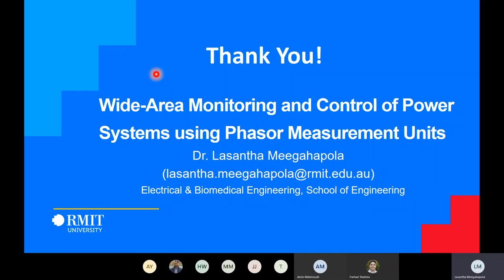I could give you one answer. Even in our test, we have shown 6 cycle latency in a certain case, from the measuring point to the real-time voltage stability analysis point. There could be latencies that go up to 4 to 5 cycles as well. But the algorithm that we have, the improved quadrature demodulation technique, can handle even 0.5 cycle to 1 cycle.